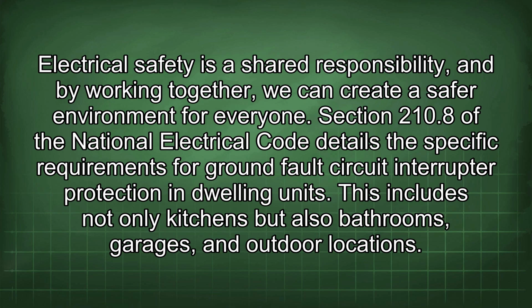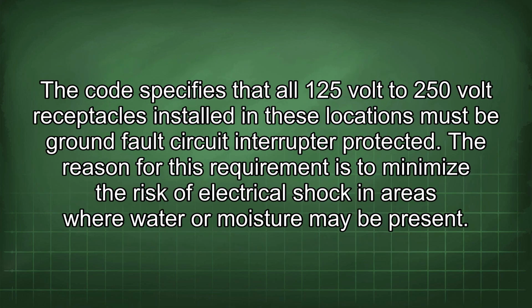Section 210.8 of the National Electrical Code details the specific requirements for ground fault circuit interrupter protection in dwelling units. This includes not only kitchens but also bathrooms, garages, and outdoor locations. The code specifies that all 125 volt to 250 volt receptacles installed in these locations must be ground fault circuit interrupter protected. The reason for this requirement is to minimize the risk of electrical shock in areas where water or moisture may be present.